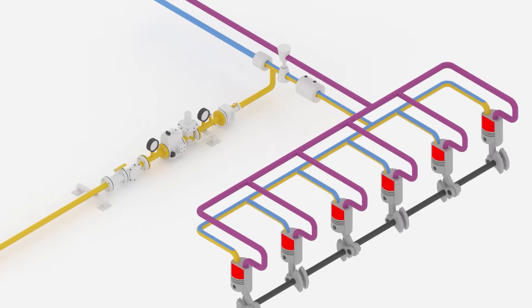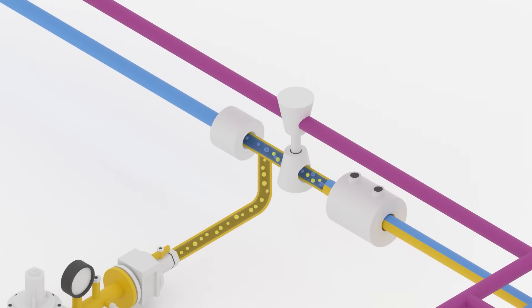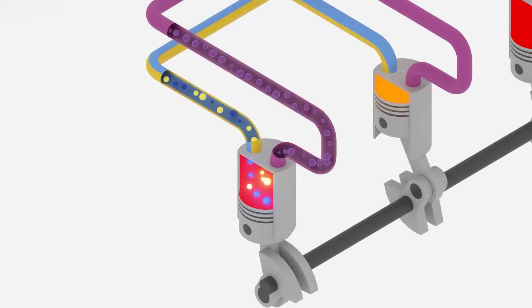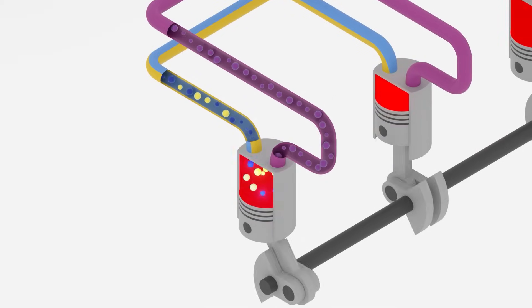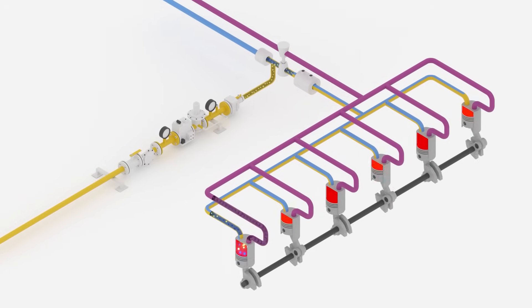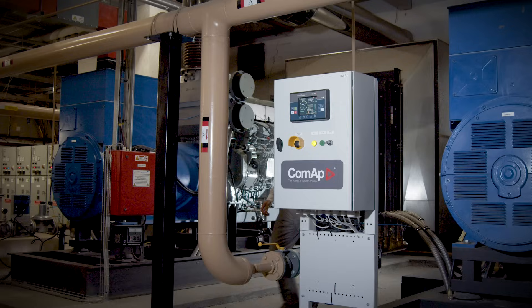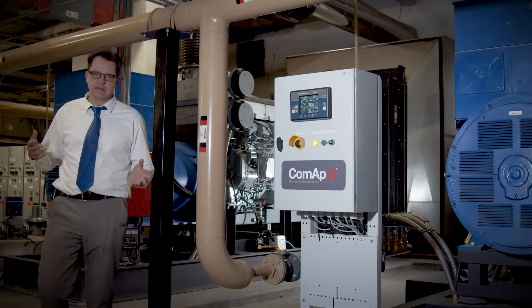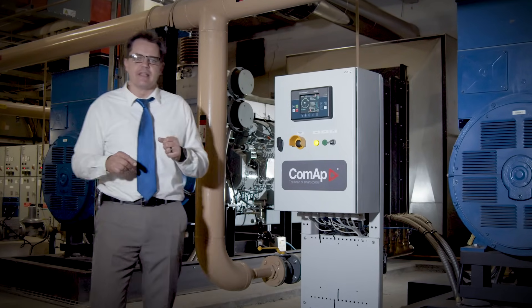This is what makes the conversion so powerful — it's a bolt-on system that transforms your existing generator. The gas train blends natural gas into the engine manifold without altering pistons, heads, or cooling systems. With safety checks and flow monitoring built in, the system performs reliably under load.